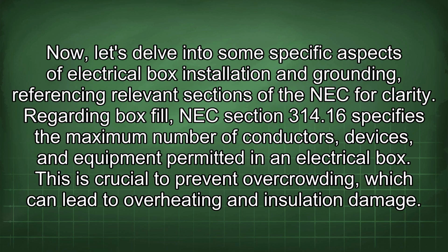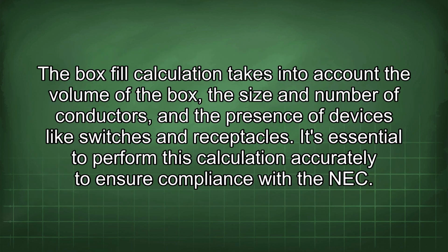Now let's delve into some specific aspects of electrical box installation and grounding, referencing relevant sections of the NEC for clarity. Regarding box fill, NEC section 314.16 specifies the maximum number of conductors, devices, and equipment permitted in an electrical box. This is crucial to prevent overcrowding, which can lead to overheating and insulation damage. The box fill calculation takes into account the volume of the box, the size and number of conductors, and the presence of devices like switches and receptacles. It's essential to perform this calculation accurately to ensure compliance with the NEC.